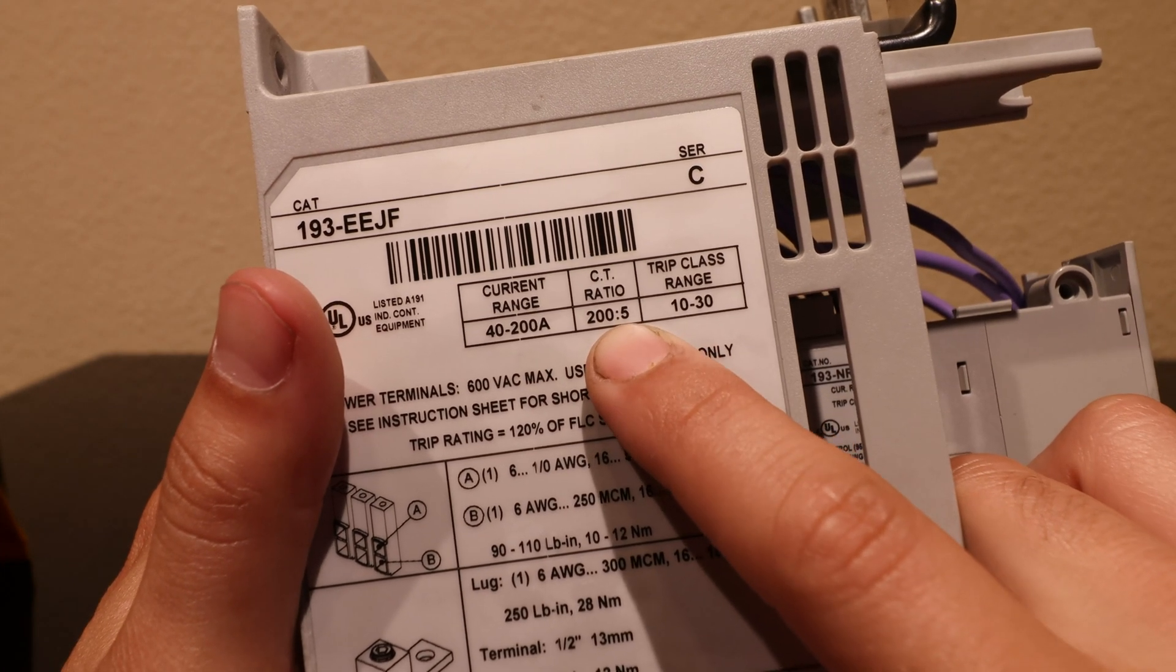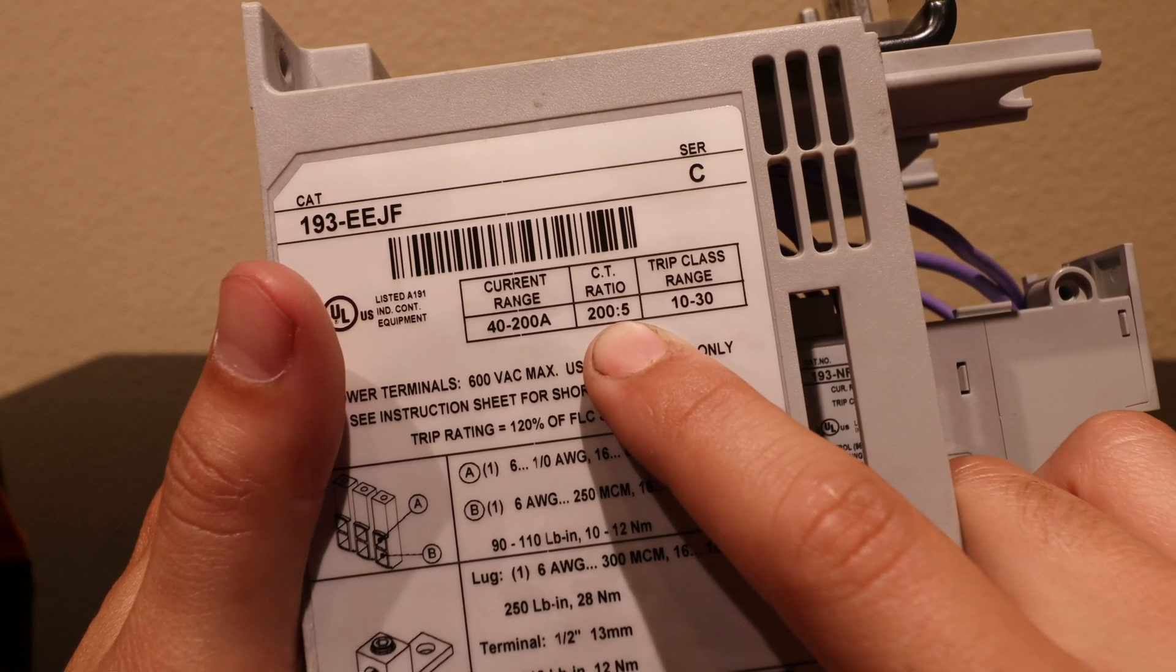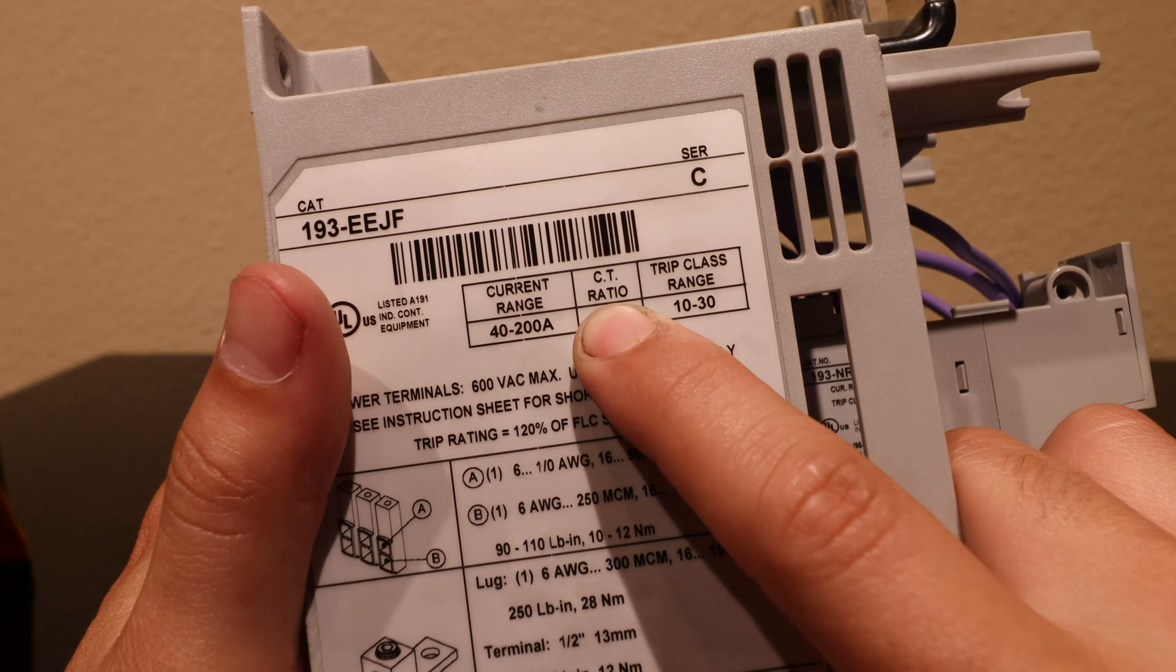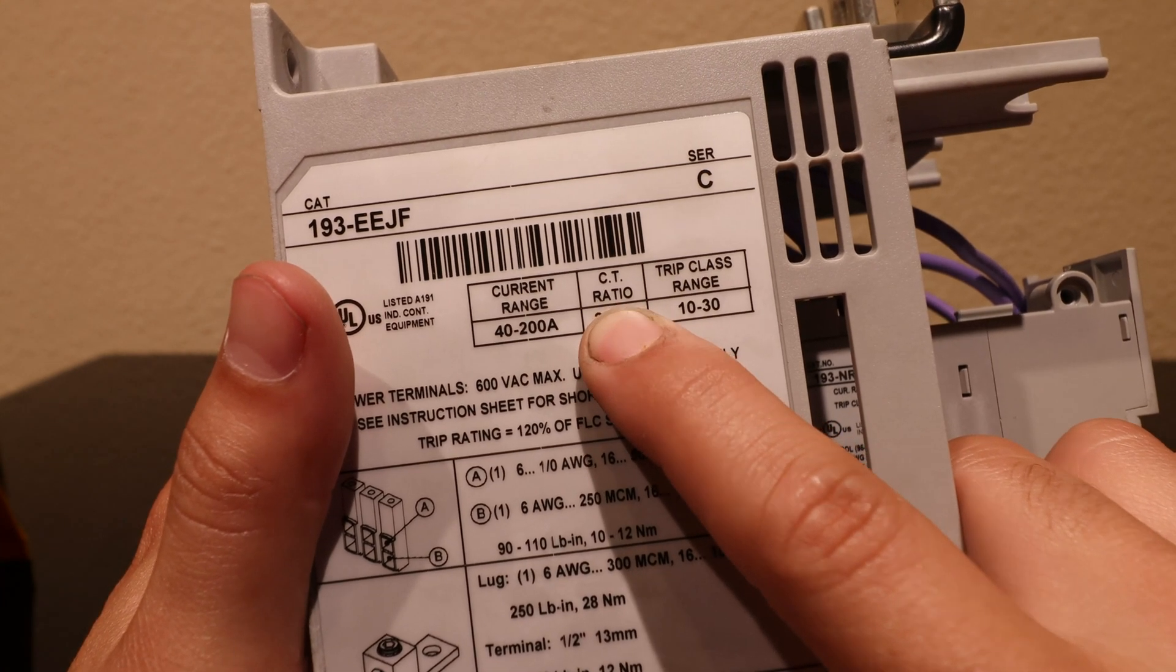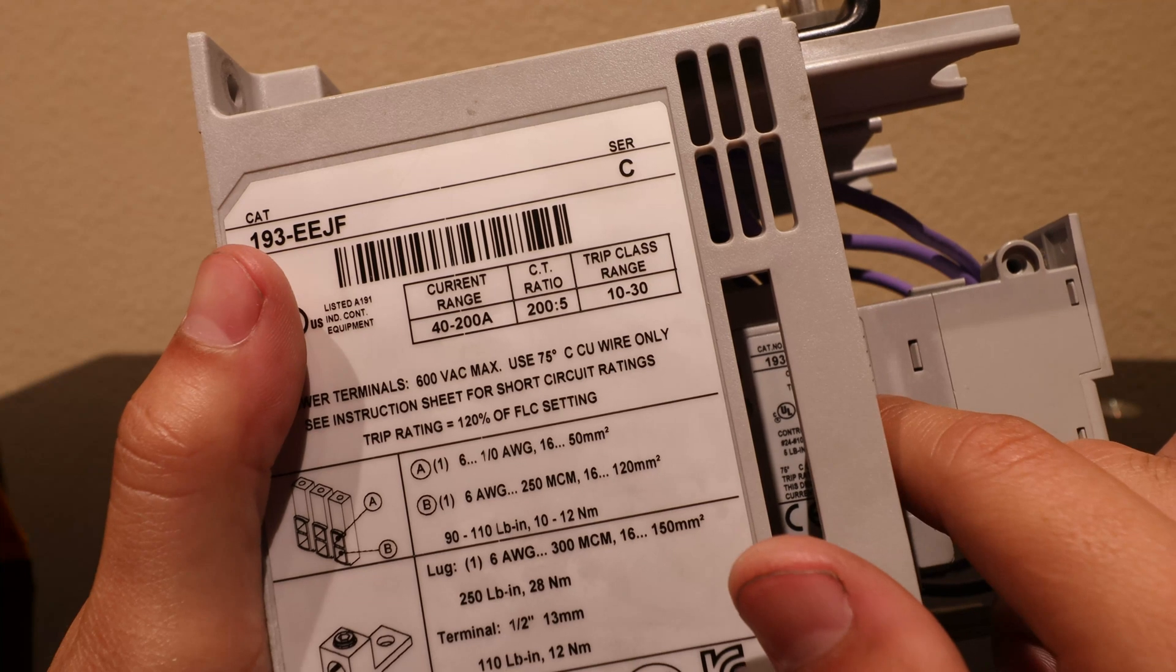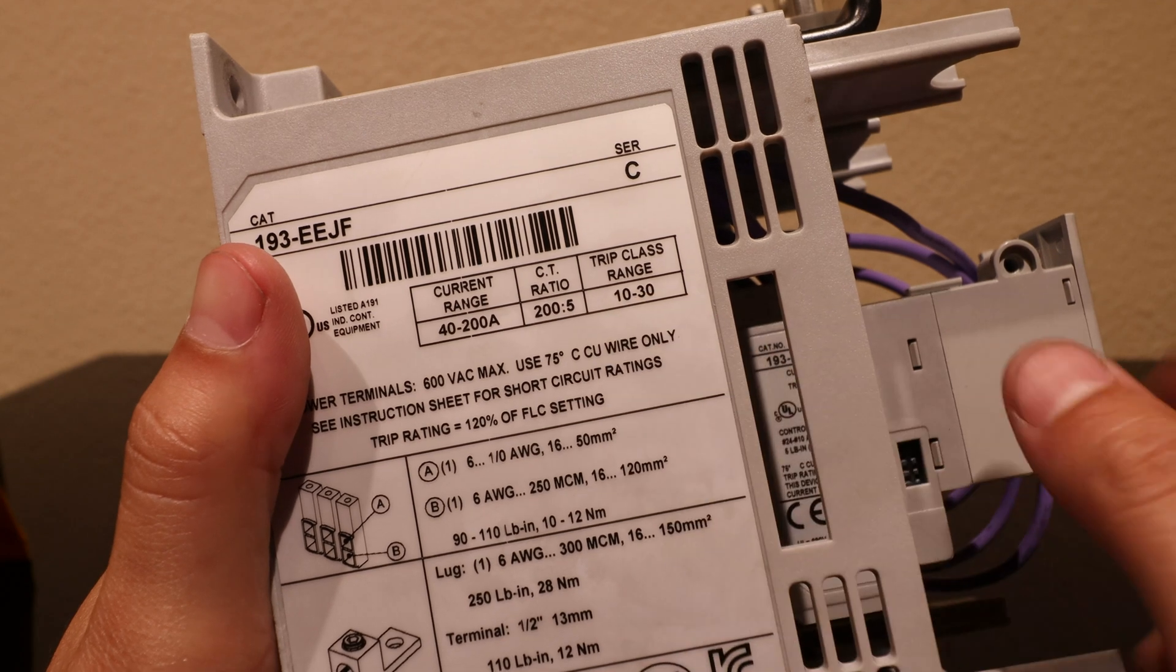The CT ratio on this is 200 to 5. I made another video about the controls for a 200 horsepower air compressor and CT ratio was mentioned in that. Basically CT stands for current transformer. It sort of like a voltage transformer - it transforms the current down to an amount that this little electronic doodad can read and work off of. Just like on the other side of the overload, it mentions the trip class range from 10 to 30.